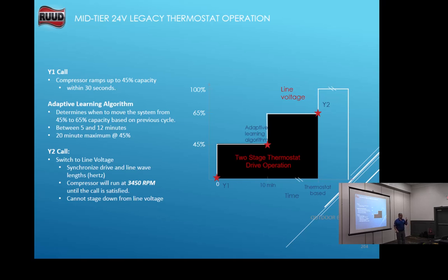Then, between 5 and 12 minutes, it goes from 45 to 65%. Second speed, first stage. Okay? You see where the confusion kind of gets in? It's not a 3-stage compressor. It's 3 speeds, but 2 stages. So, from 0 to 45% is speed 1, and then from here to here is speed 2. It's not variable in between. It ramps up to this speed for 30 seconds, and then after 30 seconds it goes to this speed. And it's staying right there straight.